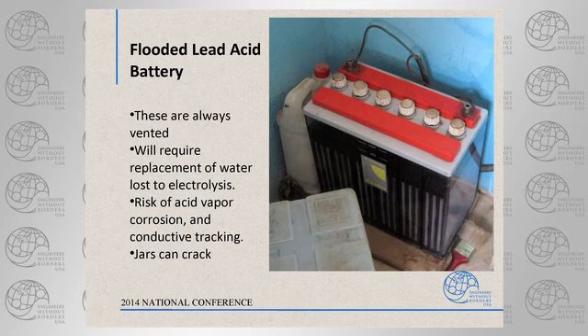Anywhere inside there, it'll ignite, and when it ignites, you remember the little pictures of the Hindenburg? That's a slow one in comparison to what can happen. I can show you pictures of a data center in California that literally lost the roof. It blew off. So they're going to require replacement of water. These are caps that can be unscrewed to get into each of the individual six cells to check the fluid level. Because these are open vented to the atmosphere, you've got a risk of some acid vapor mist coming out. You've also got a risk of corrosion at the terminals because they're in an acid environment.